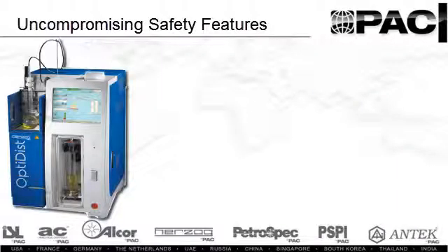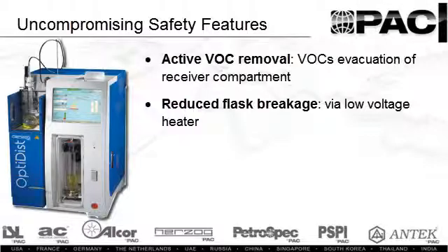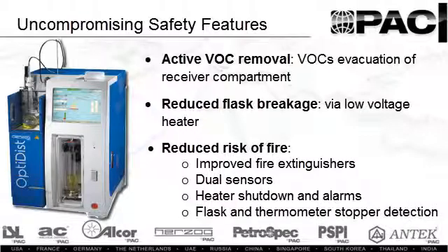Safety is paramount when working with petroleum products. The OptiDist provides VOC evacuation of the receiver compartment and uses a low voltage heater for the heater compartment. The automatic heater shutdown, alarms, and improved fire extinguishing nozzles with dual fire sensors provide uncompromising safety benefits.